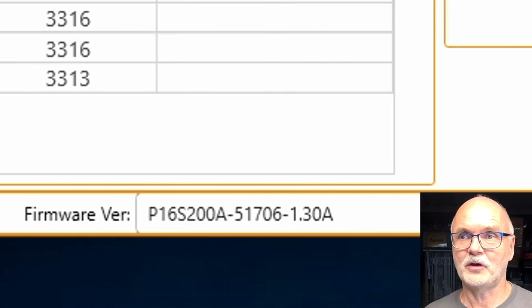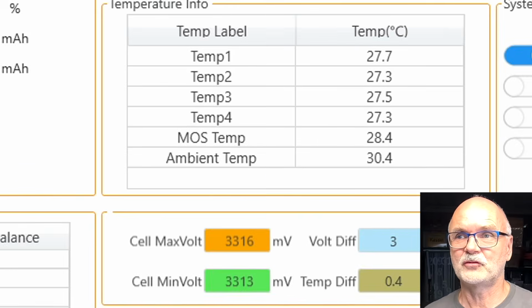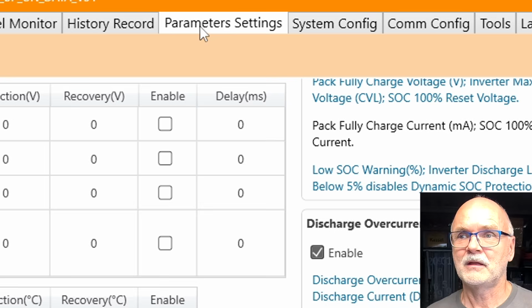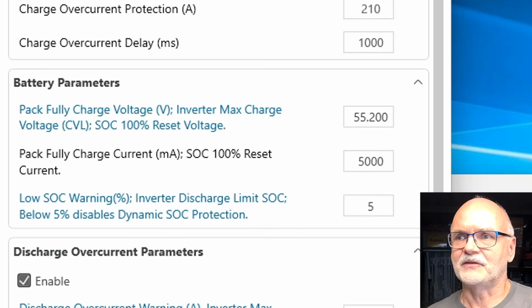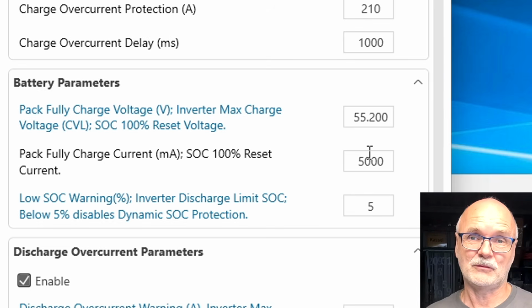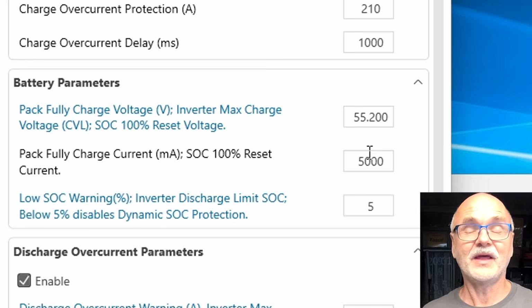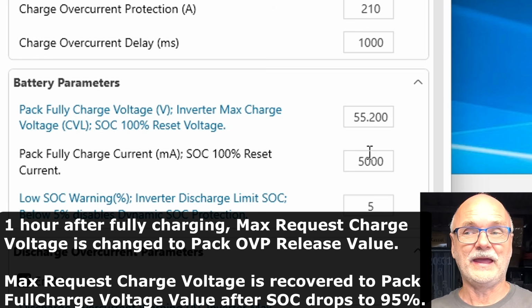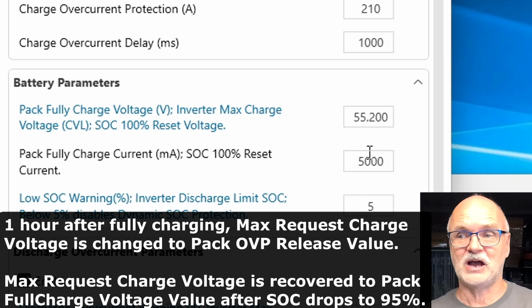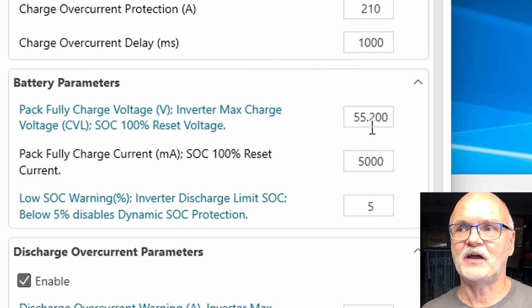Anyway, we're at 130 now, so we go back into the parameter settings. What's going to happen is we're charging to 55.2 volts. If the current goes under 5 amps, the BMS resets to 100%, and then the battery stays there for exactly 1 hour. That's what it says down there: 1 hour after fully charging, it keeps the 55.2 volts.